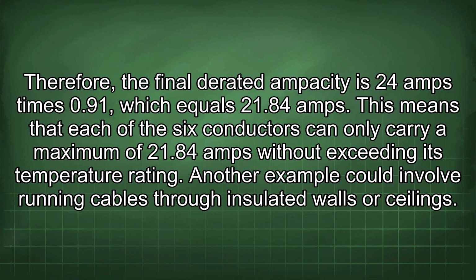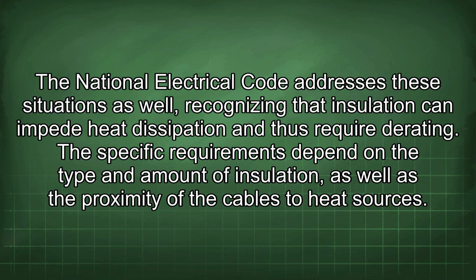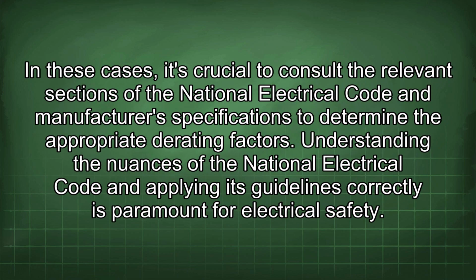Another example could involve running cables through insulated walls or ceilings. The National Electrical Code addresses these situations as well, recognizing that insulation can impede heat dissipation and thus require derating. The specific requirements depend on the type and amount of insulation, as well as the proximity of the cables to heat sources. In these cases, it's crucial to consult the relevant sections of the National Electrical Code and manufacturer's specifications to determine the appropriate derating factors.